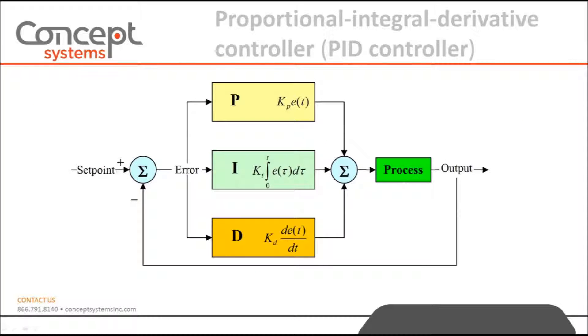A PID controller consists of three parts. First, the proportional term is the amount added to the output based on the current error; the proportional gain is a multiplier. Second, the integral term is the amount added to the output based on the sum of the previous errors. Third, the derivative term is the amount subtracted from the output based on the rate of change of the current error.